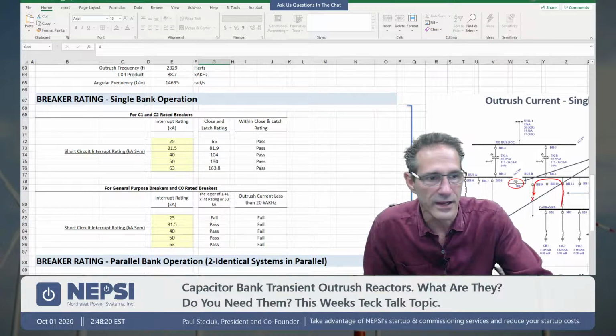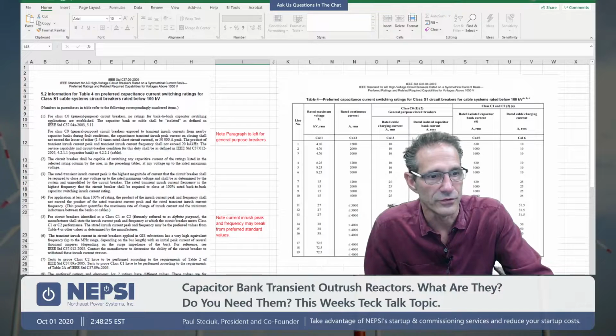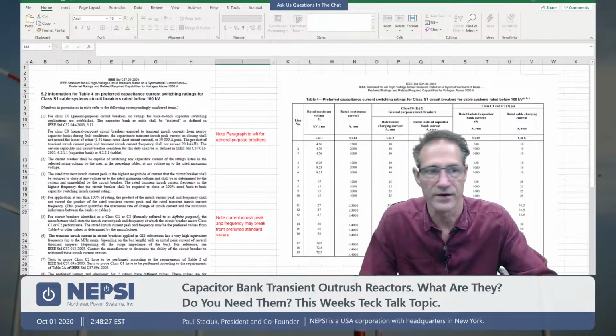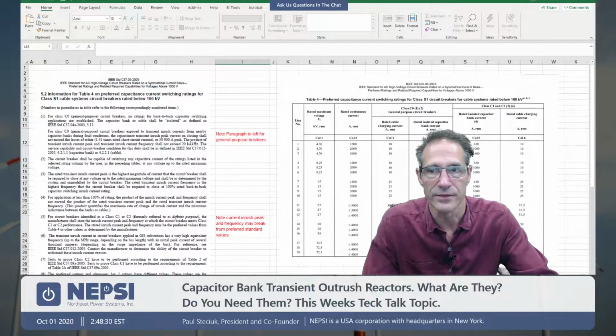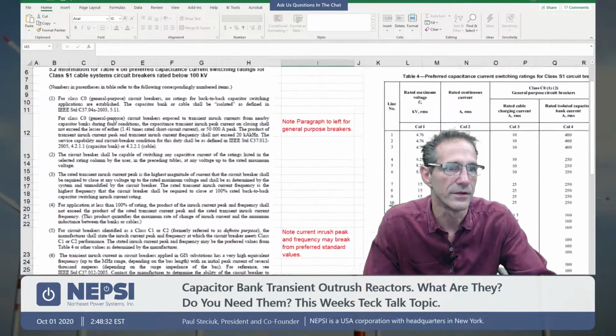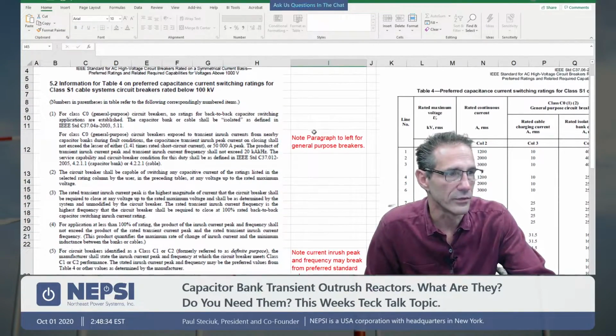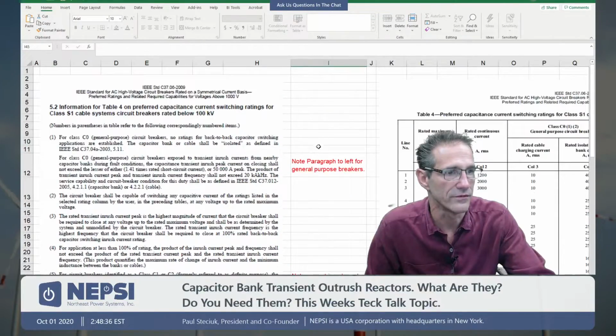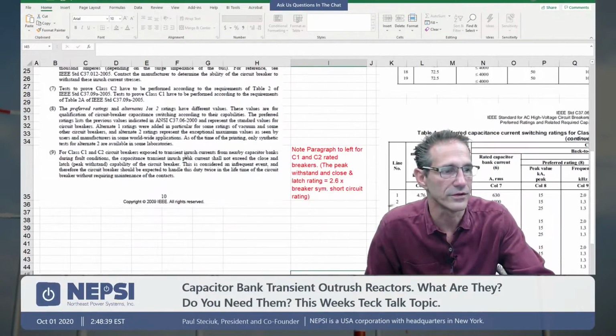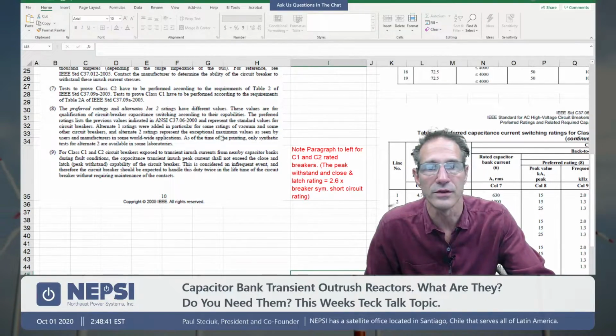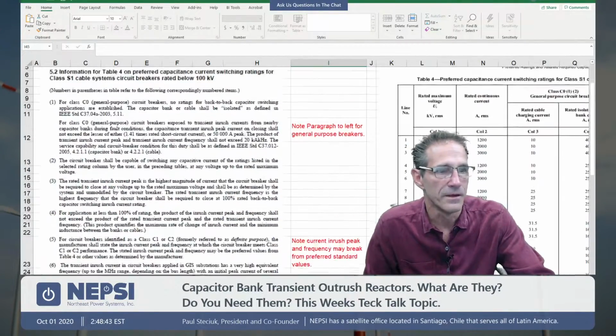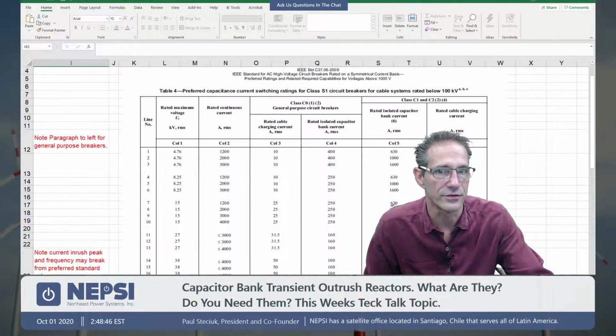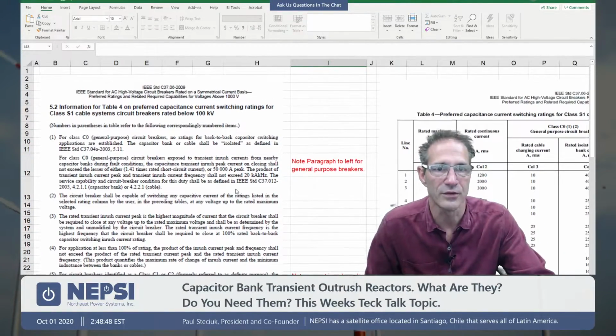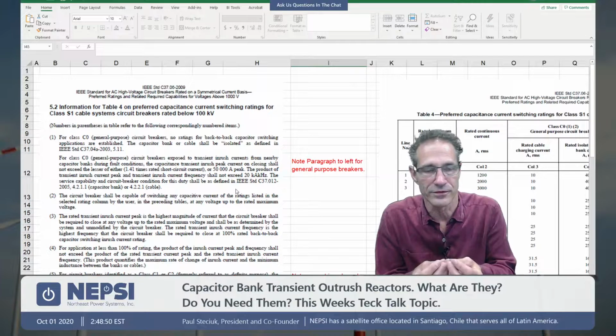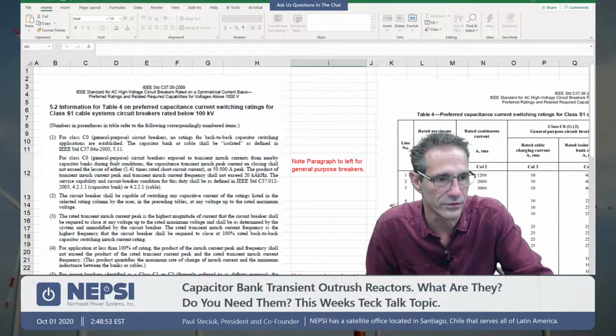And you can go to the standards, and that's actually on tab 2 of this spreadsheet tool, C37.06, and in there you can find where they talk about the C0 rating, and we make some notes over here about these various footnotes within the standards and what the C1 and the C0 rating does for you, as well as the tables that are associated with those standards. So we're just peeling apart the standard a little bit and telling you, hey, these are the parts that matter. So you don't have to go review the whole standard.